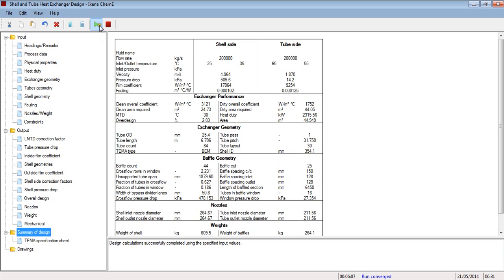Okay, so now we have a design here. As you can see, heat transfer coefficient 3121. If you consider fouling, it would be 1752. Pressure drop is slightly lower. This is slightly low, but that is fine. This is slightly low. This is roughly 5 atmosphere. This is high. Number of tubes 84.